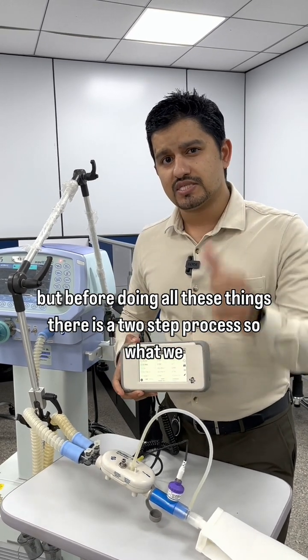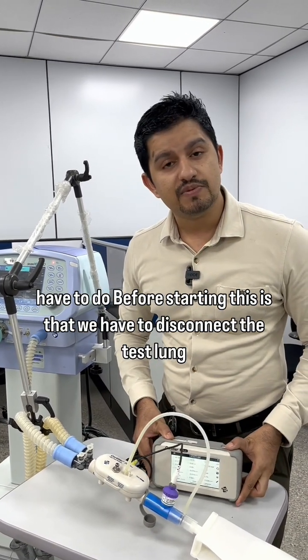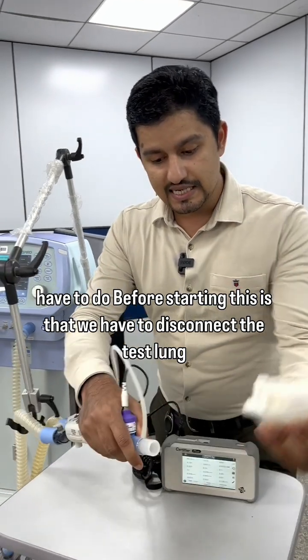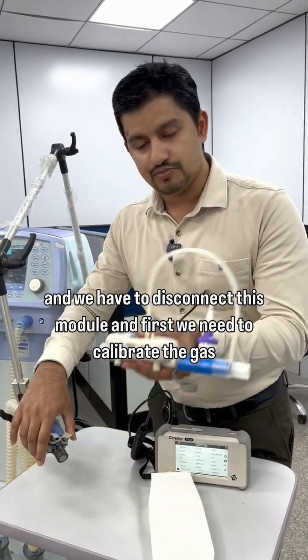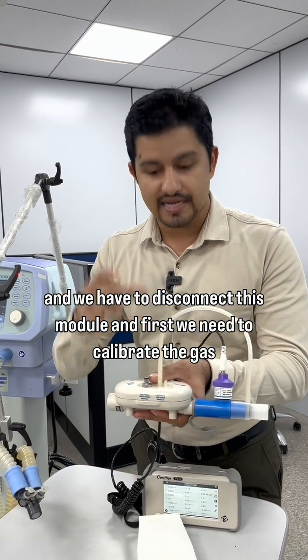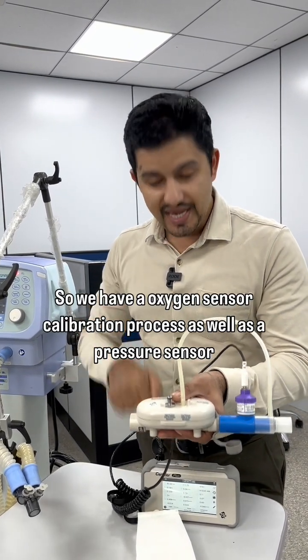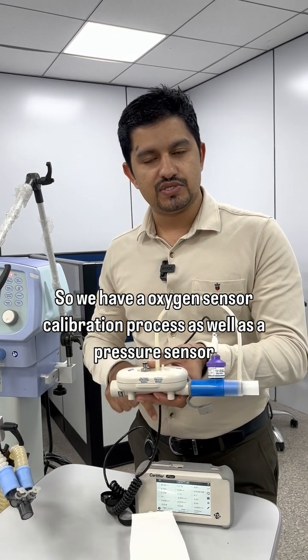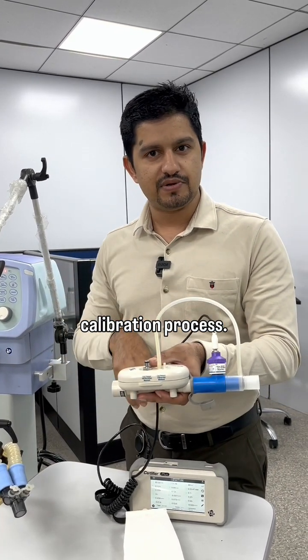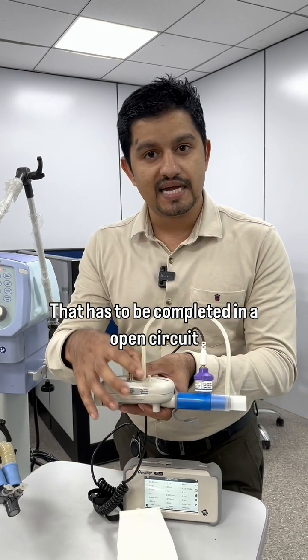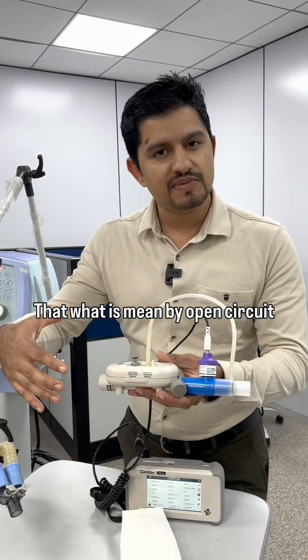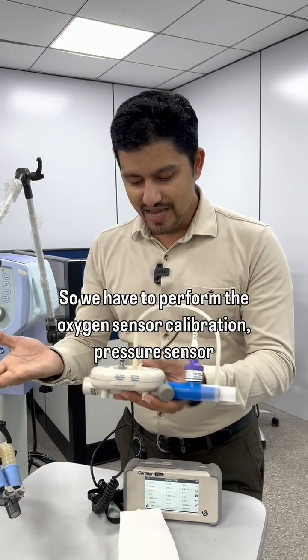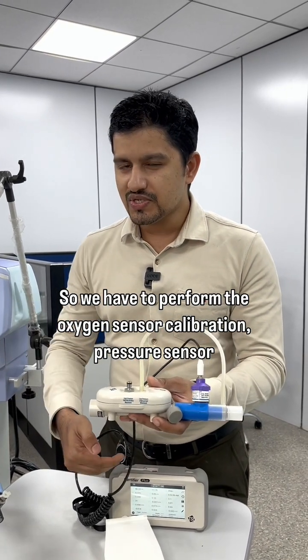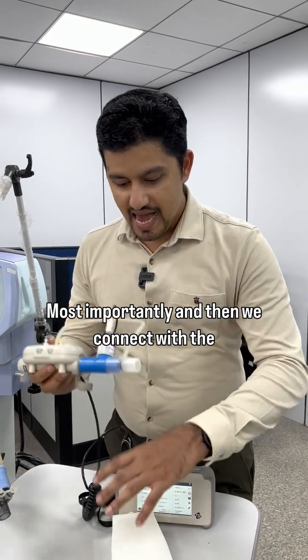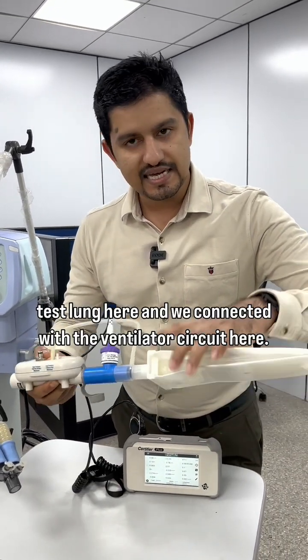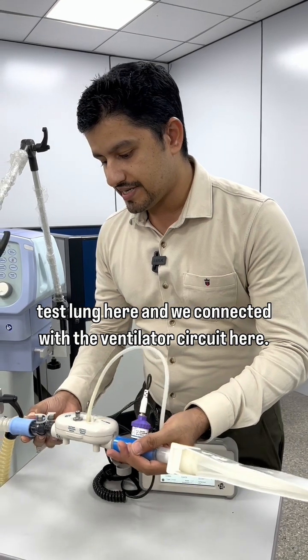But before doing all these things, there is a two-step process. Before starting, we have to disconnect the test lung and disconnect this module. First we need to calibrate the gas flow module here. We have an oxygen sensor calibration process as well as a pressure sensor calibration process. There are switches for that. That has to be completed in an open circuit. What is meant by open circuit? It's not connected anywhere. So we do the oxygen sensor calibration and the pressure sensor calibration, most importantly, and then we connect it with the test lung here and with the ventilator circuit here.